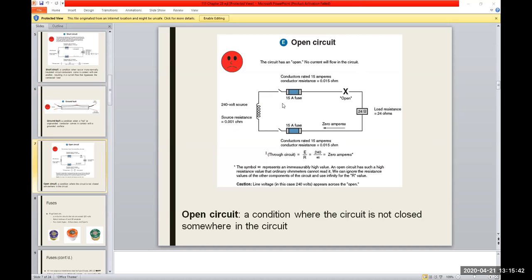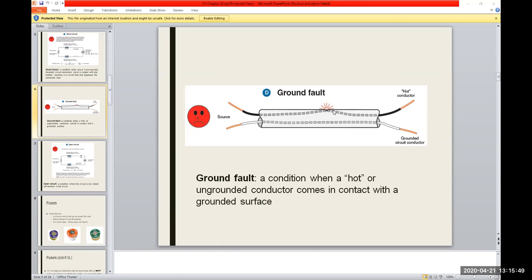We'll get into ground fault interrupters in a little bit, but that is setting up that condition. You get a ground fault where you get a break in the line or some kind of short. This could happen, and there are different things that can cause a situation like this. Somebody drove a nail through the wall. You could even have critters. I had one in this house too, on my AC unit outside.